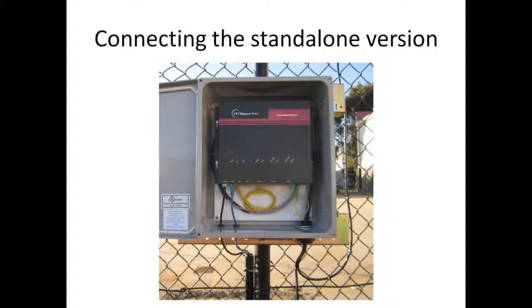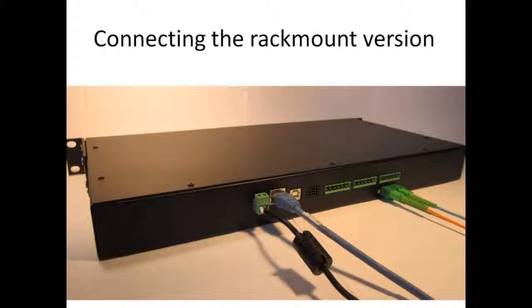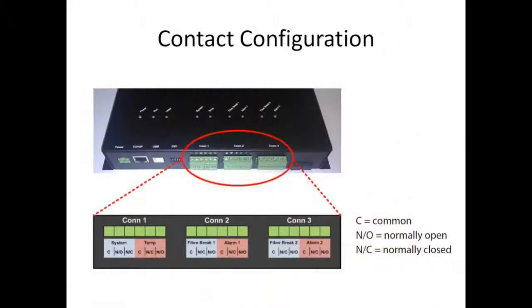The connections for the remote and the rack mount versions are the same. You'll note the three square connectors on the back. They're your relay contact outputs. The Form C contacts can be configured in normally open or normally closed.